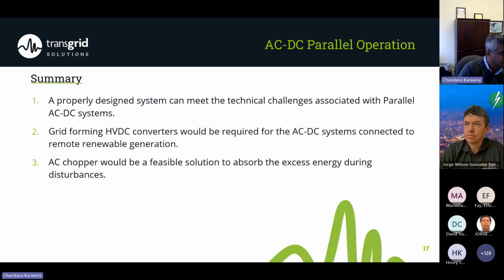And what we know from the manufacturers is that they are reluctant to offer LCC because they are mainly focusing on VSC. The other thing is that since this system is connected to a weak system and we need to operate in grid forming mode, with LCC it would be quite challenging to go for grid forming with a weak system, and we may need a lot of synchronous condensers and so on. But VSC would be a better solution for sure. And considering today's market, I would definitely say that grid forming VSC would be the solution.